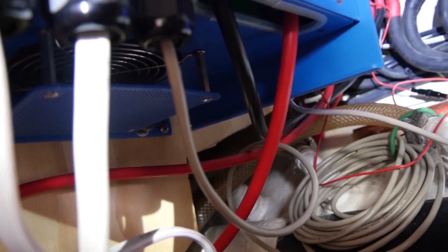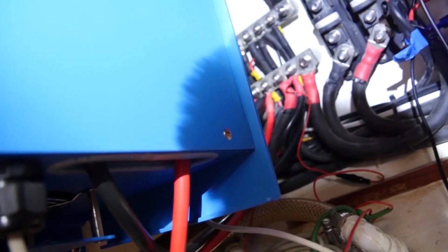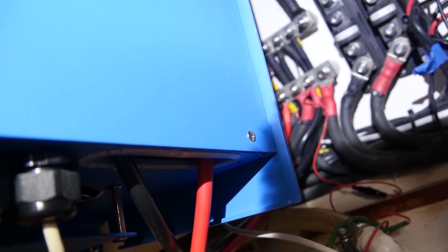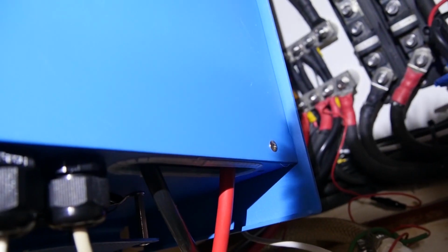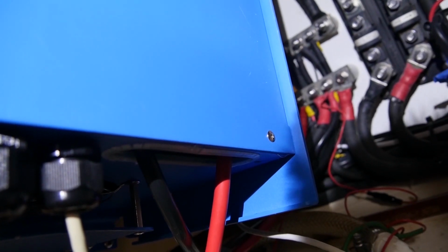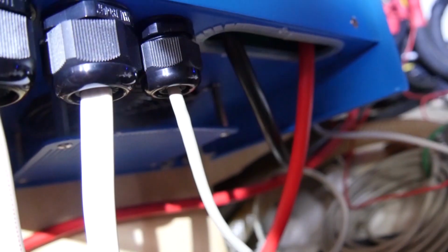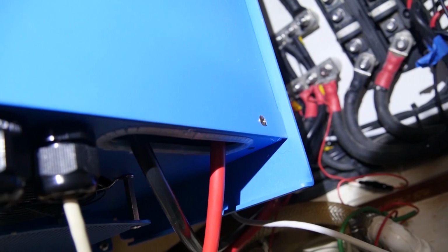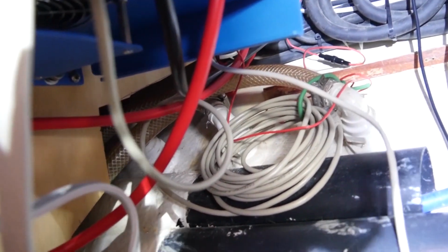We've been finding that when we use the inverter we get an unacceptable voltage drop, causing the inverter to reset at very high amperages - this happens when using big appliances like the espresso machine, or sometimes the microwave at high power. The red and black negative and positive cables going in were supposed to be the right size, but I've bought thicker, lower gauge cables to go into the inverter instead. I'm going to change those, which should hopefully stop the problem.